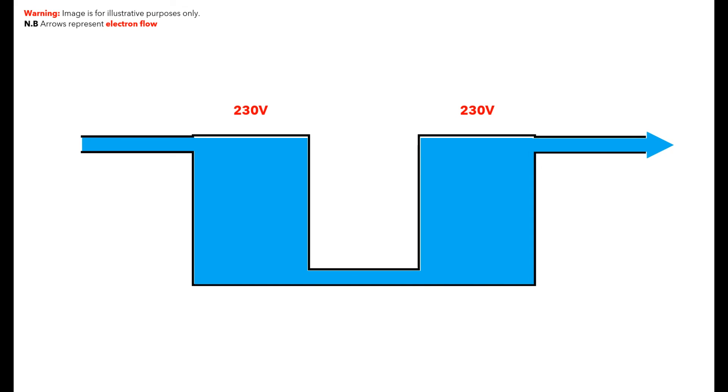However, if current isn't flowing, then the safety devices will not operate, so the reality is that we need somewhere for that current to flow, in order to keep the current flowing fast enough and long enough, that the protective devices will operate and switch off the supply.